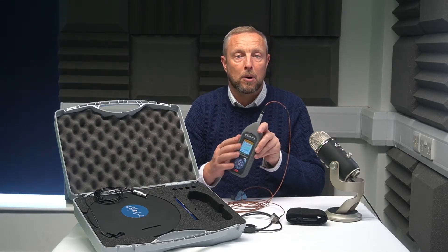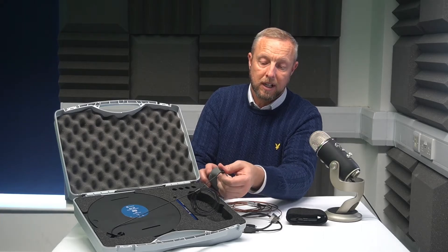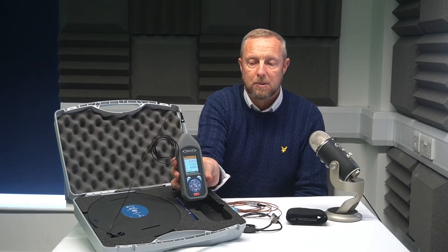It's exactly the same for whole body vibration. Just unclip the sensor, take the whole body vibration sensor, and click it into the top of the meter. It will go through its auto test, which takes about 60 seconds.